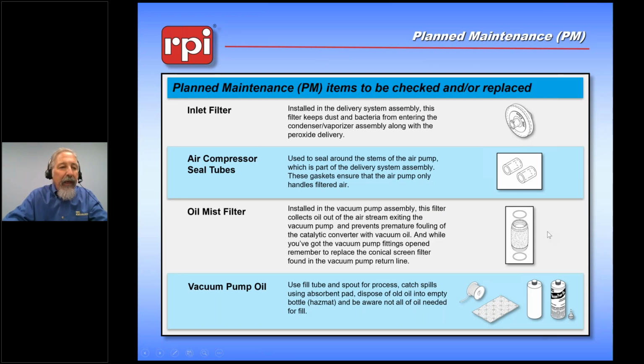So again, what do we have included in these planned maintenance kits, and why are we checking them? Well, way back at the very beginning of the system, we talked about how the hydrogen peroxide was transferred from the cartridges into the vaporizer condenser using sterile air. And this is the sterile air filter that prevents any contamination from flowing in with the hydrogen peroxide. There are also tubes that keep the valves seated properly within the vaporizer condenser assembly, and there is a pump in there as well. Within the PM kit, we have an oil mist filter.